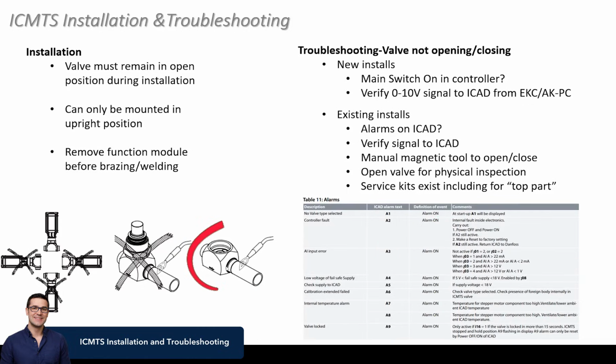you have the top part, it's called, which I kind of associate with being the actuator, but they call it the top part of the valve. That does need to be removed in an ICMTS when it's being installed in the system. So we really do just want the valve body before it's welded into the rack. As you can see, this third depiction on the right side of the 3 there at the bottom. Okay, yeah. So you definitely take out the top part on the ICMTS valve.